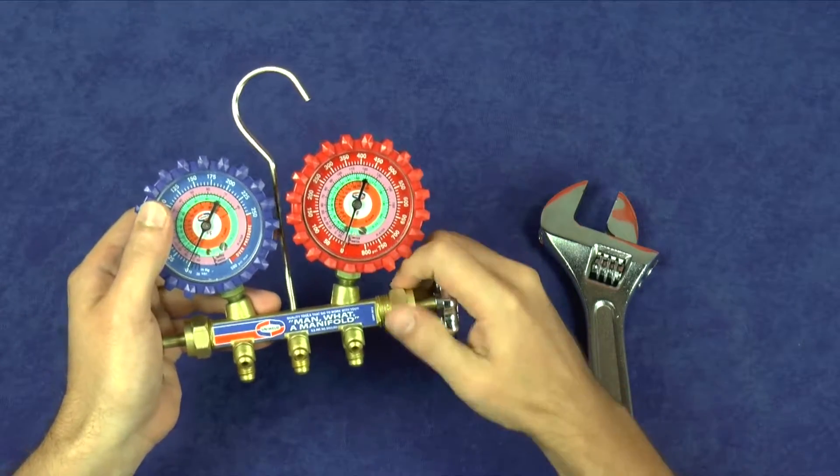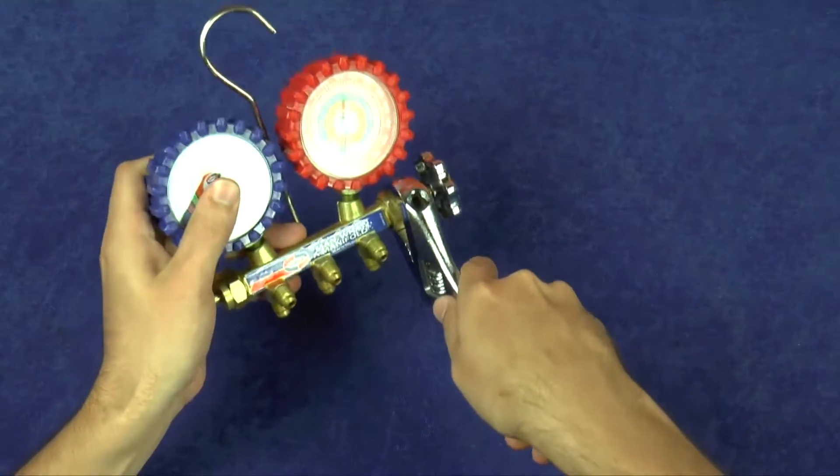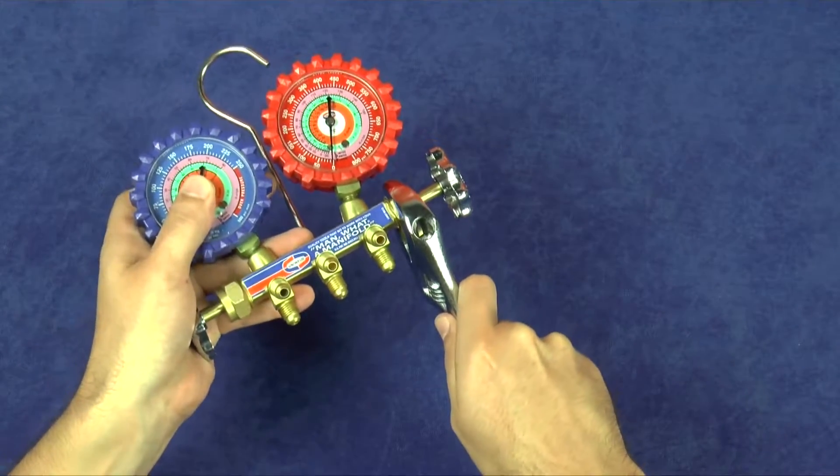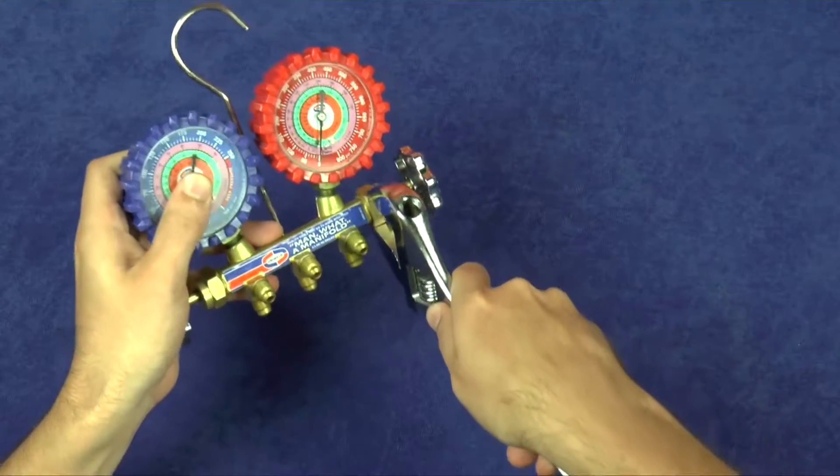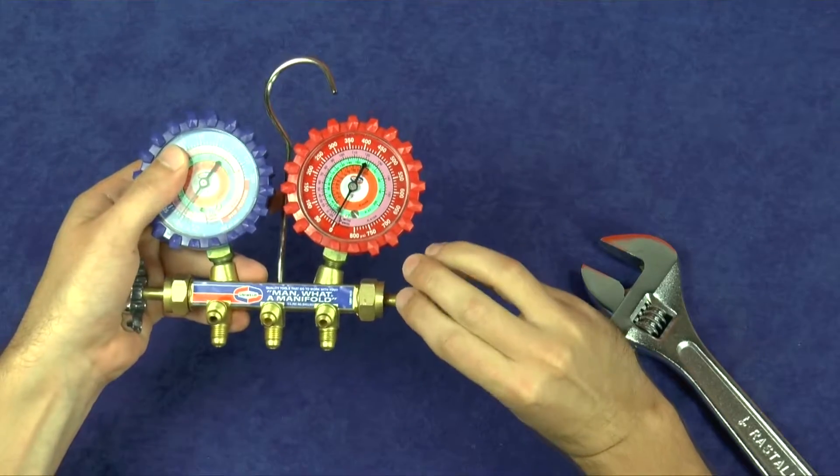The tightening of the packing nut is done by feel. The nut should be wrench tight and the hand wheel should turn to open and close the valve with some resistance. If the hand wheel feels tight and is difficult to turn, you may have over-tightened the packing nut and should loosen it slightly.